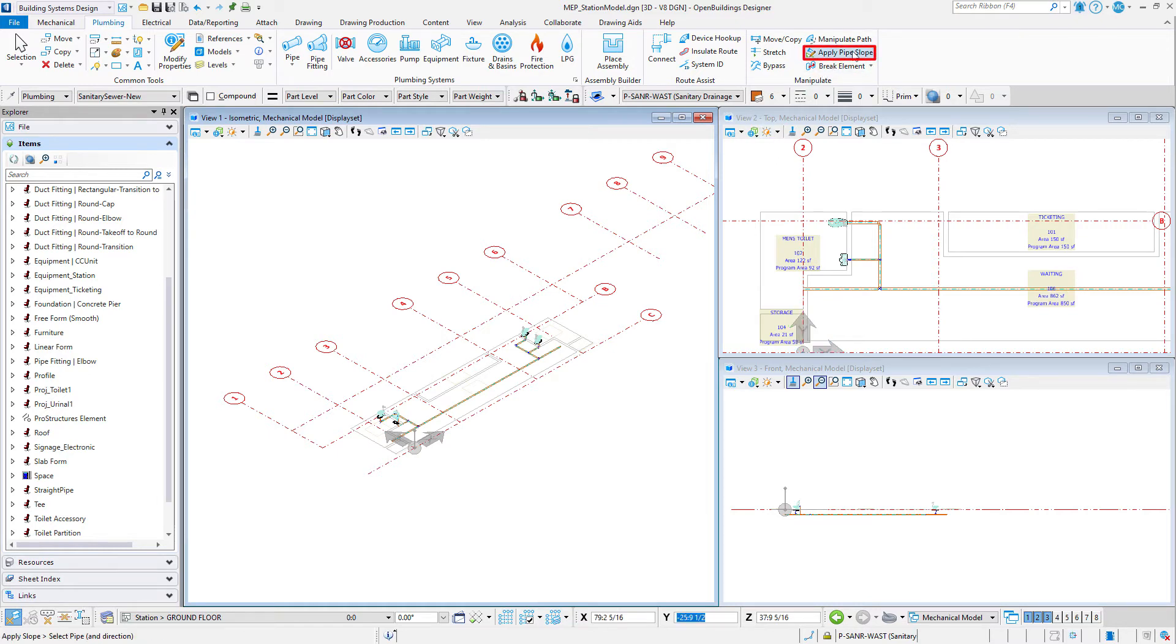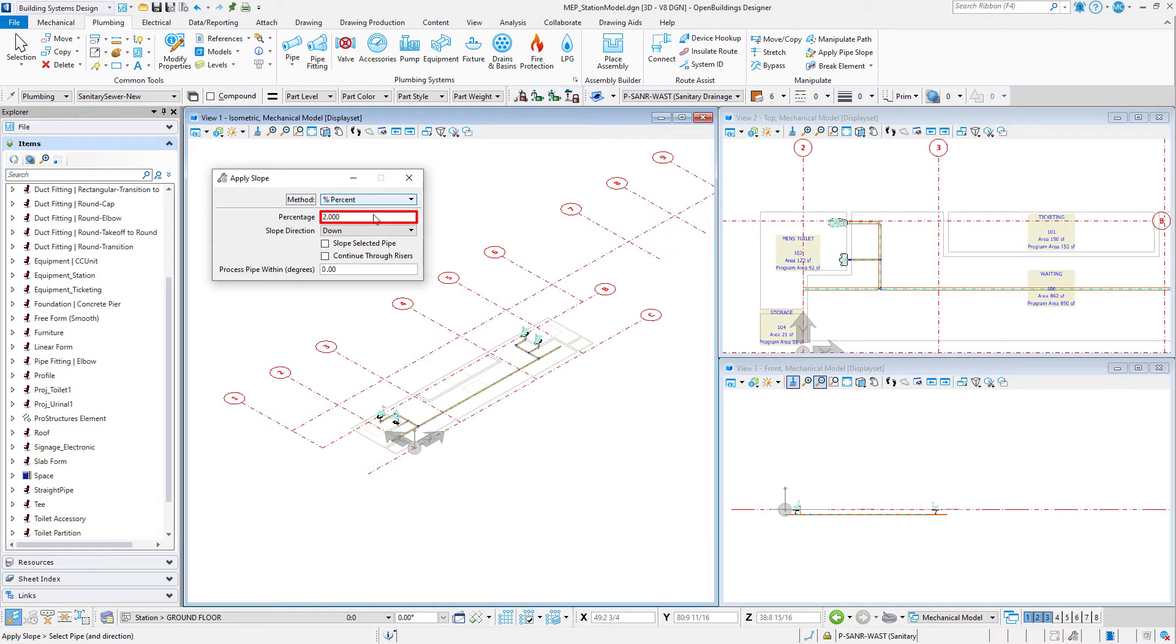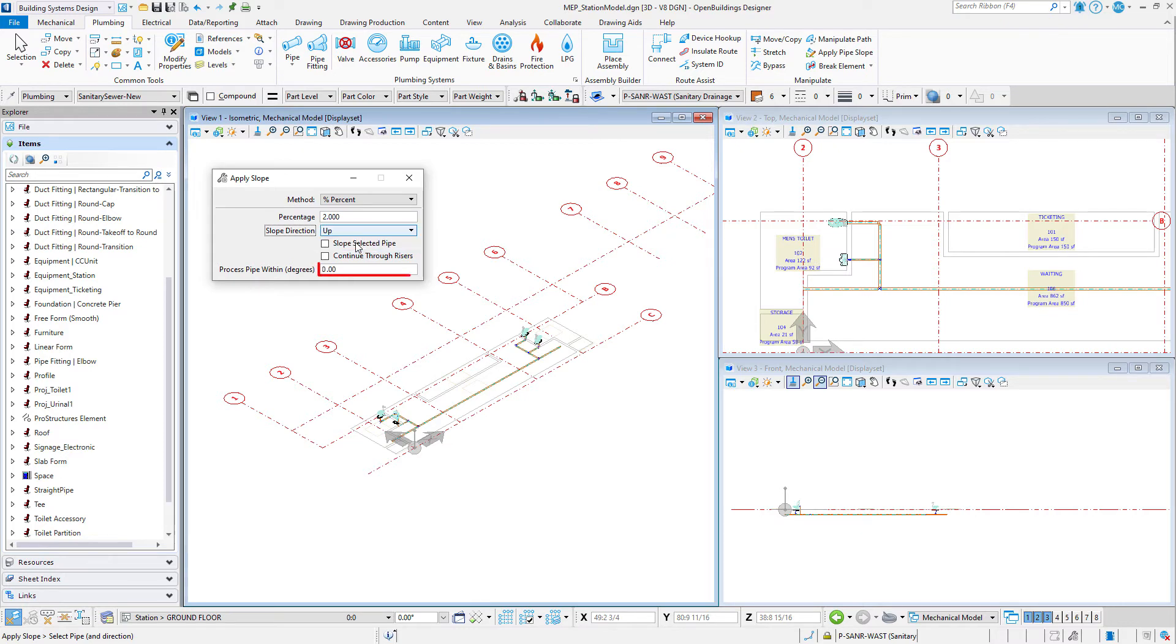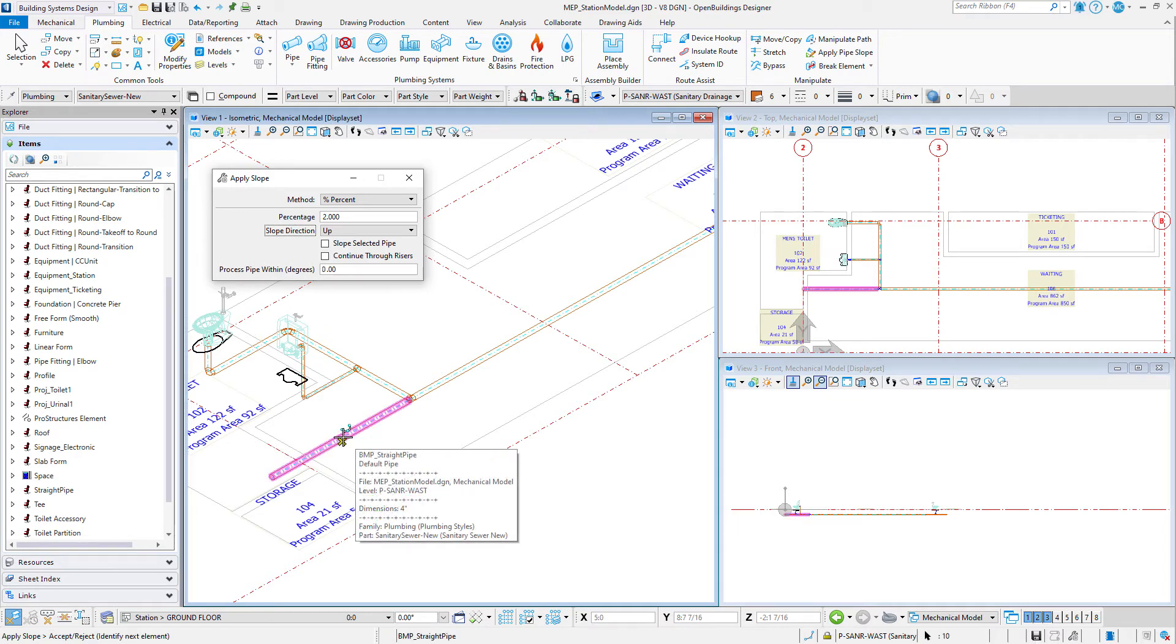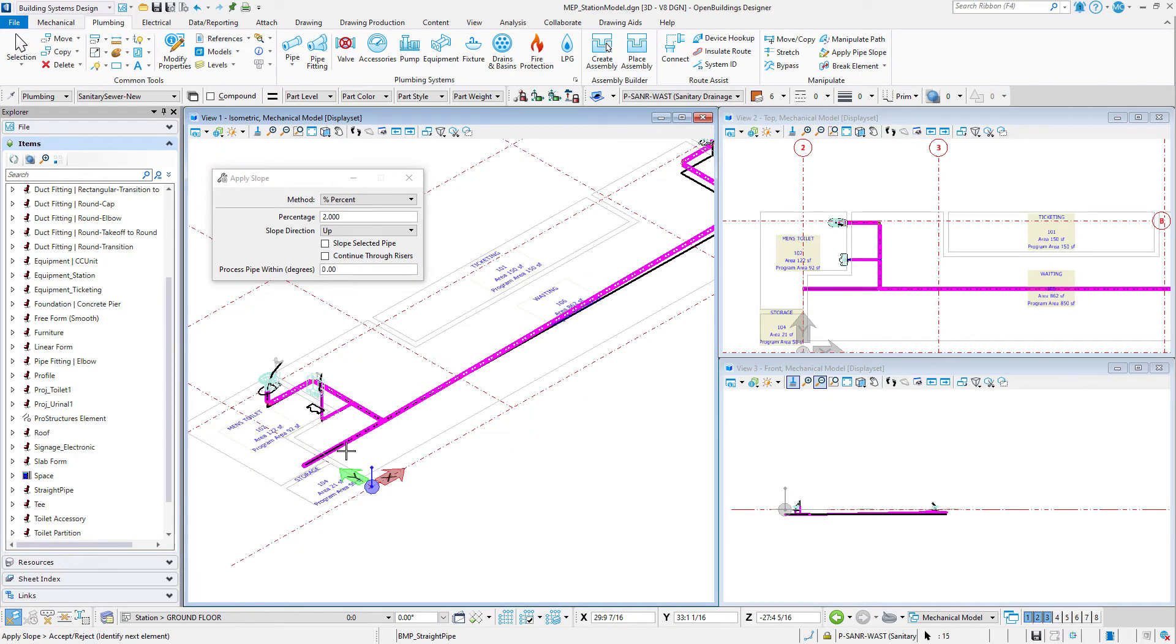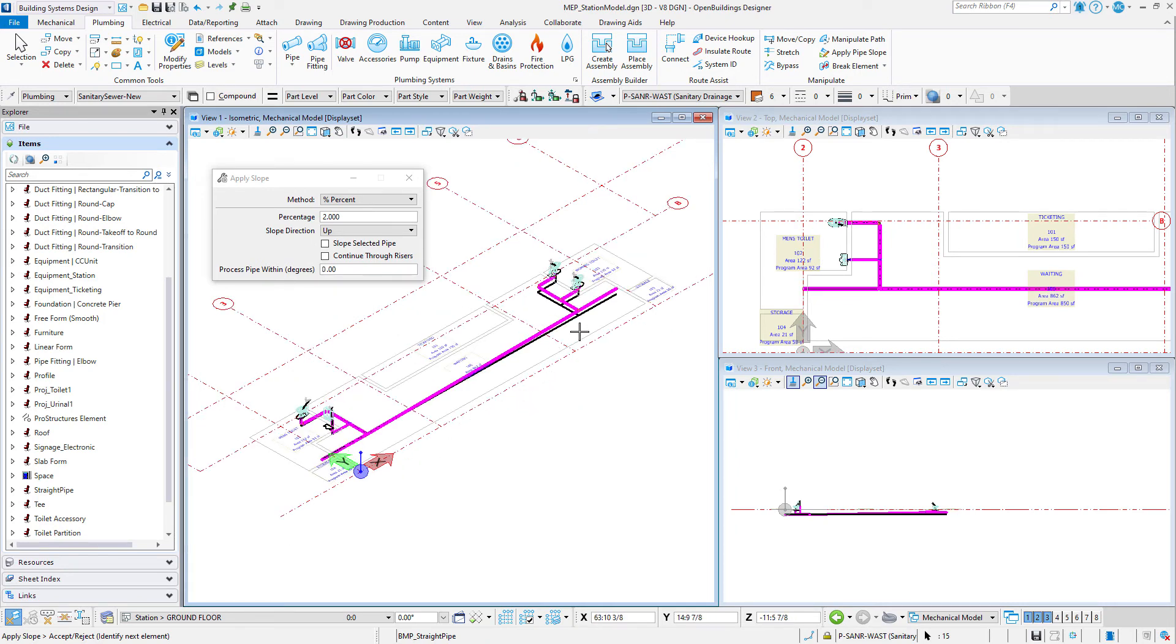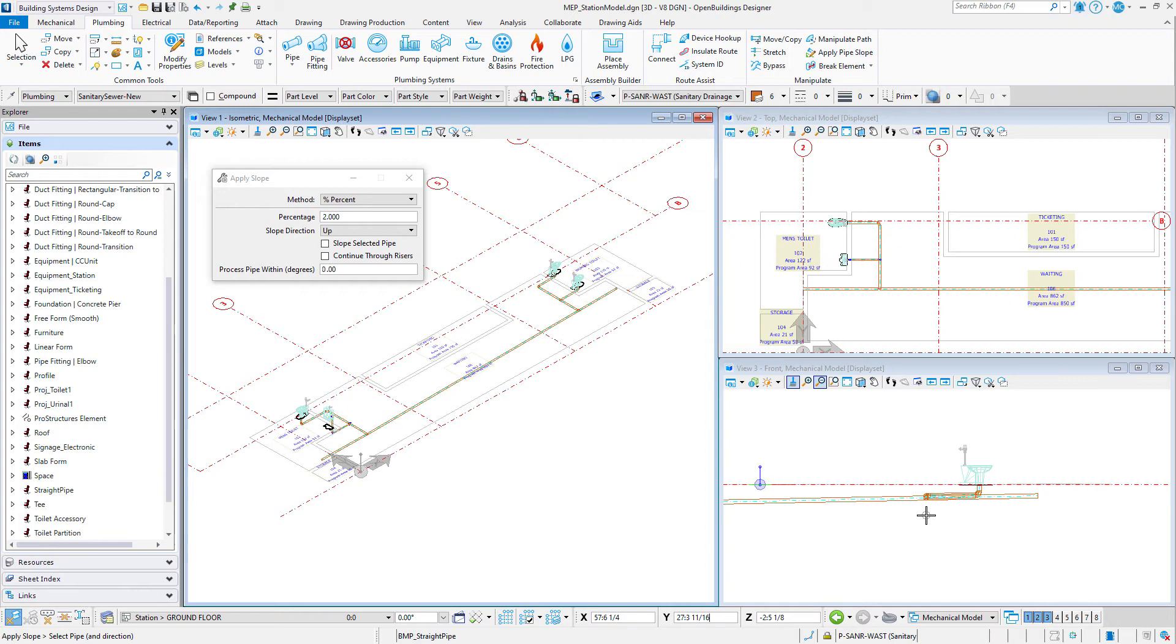So select the Apply Slope tool from the manipulate group on the plumbing tab. Set the method to percent, the percentage to two, the slope direction to up, and process pipe within zero degrees. Now select the last piece of the main pipe. A preview will show the manipulated pipe, with a single black line indicating the current location of the pipe. Then data point to accept. The pipes and corresponding fittings are adjusted to the new slope.